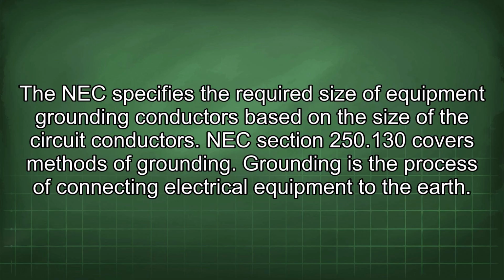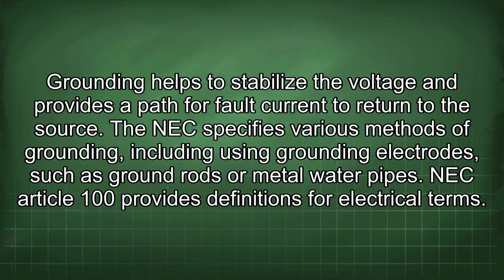NEC Section 250.130 covers methods of grounding. Grounding is the process of connecting electrical equipment to the earth. Grounding helps to stabilize the voltage and provides a path for fault current to return to the source. The NEC specifies various methods of grounding, including using grounding electrodes such as ground rods or metal water pipes.